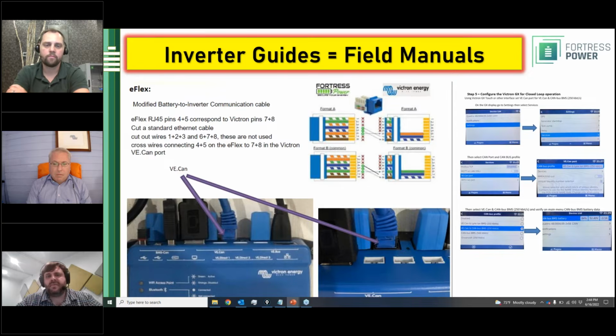Whether you're a beginner using the Ethernet keystone or making up your own communication cable, you need to be prepared to make that crossover. In this case, for the eFlex, we connect pins 4, 5, and 6 to pins 7, 8, and 6 on the Victron inverter, regardless of whether it's a type A or B format Ethernet connector.